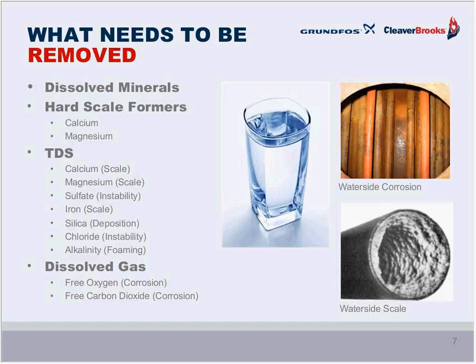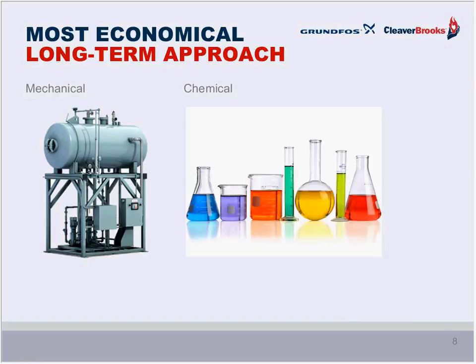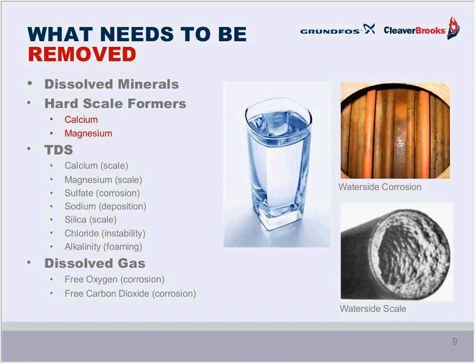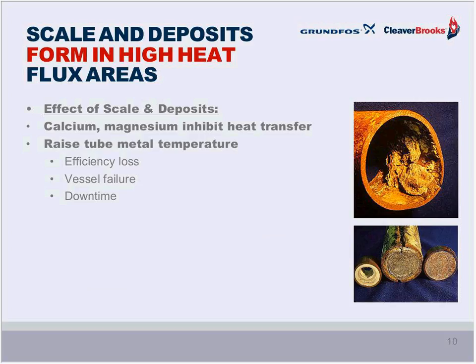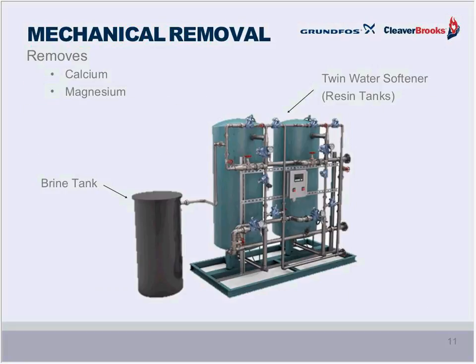That'll be next month. So in the final analysis, a successful and most economical water treatment program really boils down to two parts, both the mechanical and the chemical solution, that will then in tandem complement each other. For instance, from a mechanical perspective, we are focusing on the hard scale formers, the calcium and the magnesium. Of course, the consequences that they can cause if they're not properly controlled, well, it is imperative that a water softener be employed to remove these damaging salts.